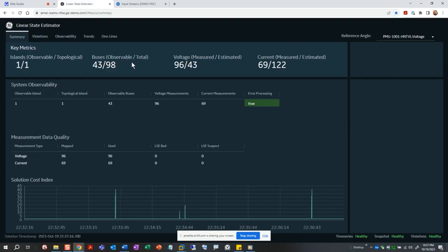Manu showed that very well in that slide. So you've got your traditional RTUs in the field bringing back data to your traditional state estimator, and then you've got PMUs feeding your linear state estimator. And then there's also some hybrid examples where those two can coincide with each other, but in this case, we're just running a linear state estimator purely off of PMU data, completely by itself.